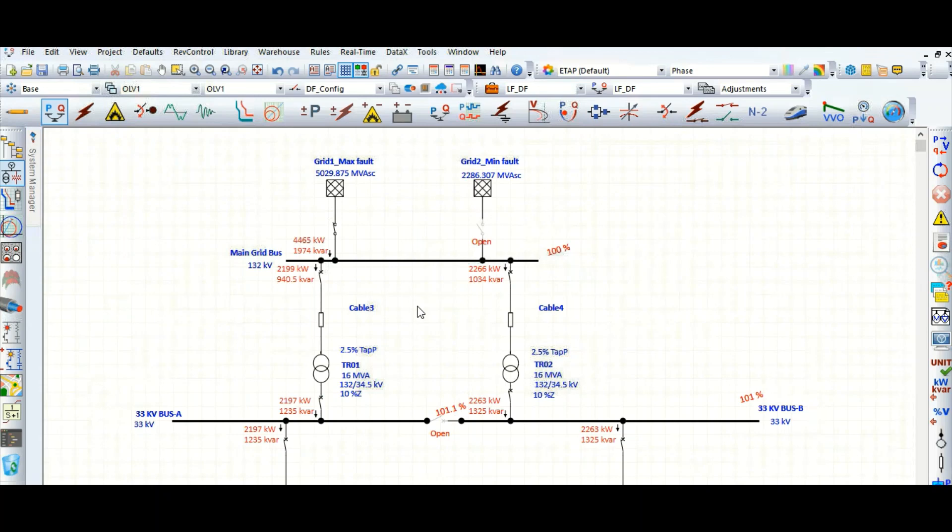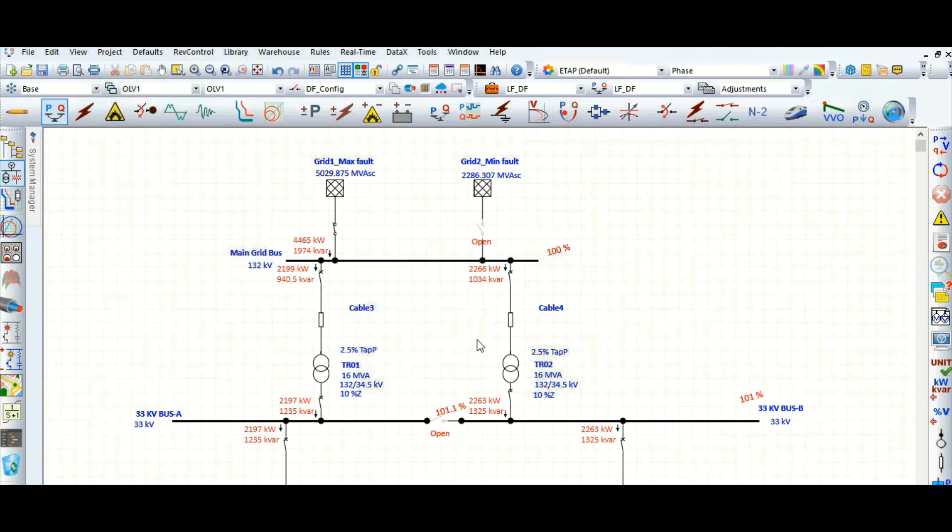Now suppose based on the operation philosophy, based on the site operation team, you are getting some data that these connected loads with this existing power system network may not be required to run simultaneously. That means some loads are running in reduced capacity or maybe some loads are totally switched off. In that case, as a power system engineer, we need to apply the load diversity factor.